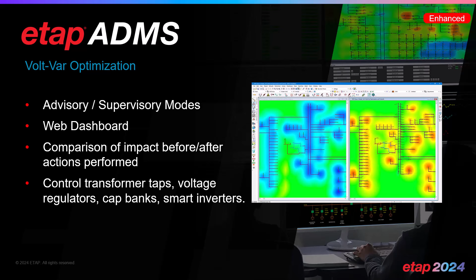We are able to control various controllable devices in the system with volt-var optimization, such as transformer taps, voltage regulators, capacitor banks, and now smart inverters.